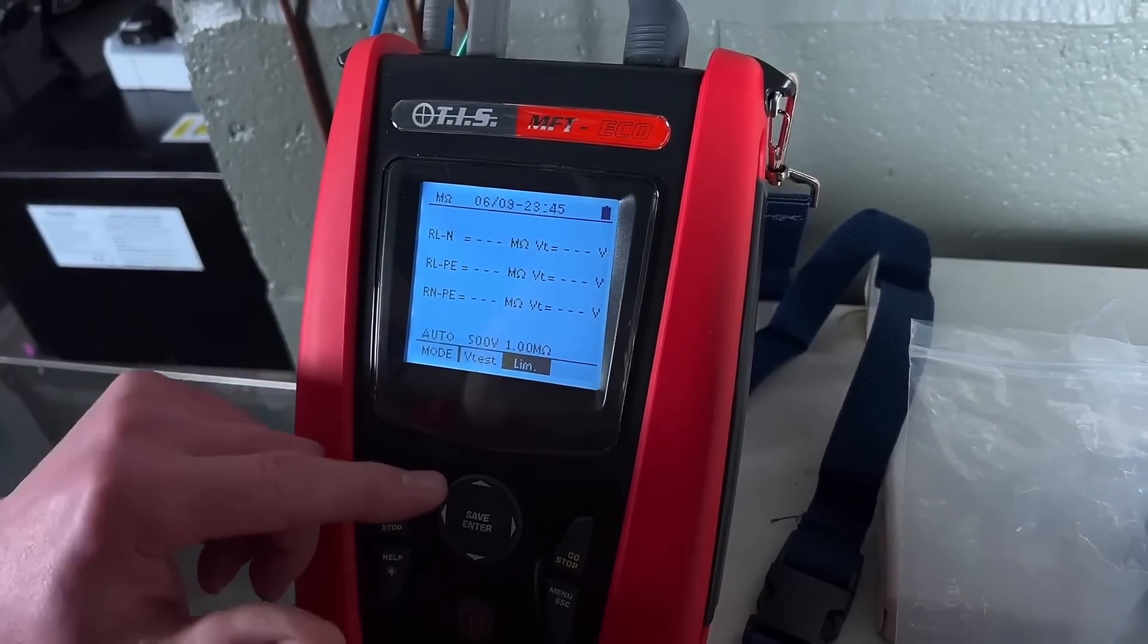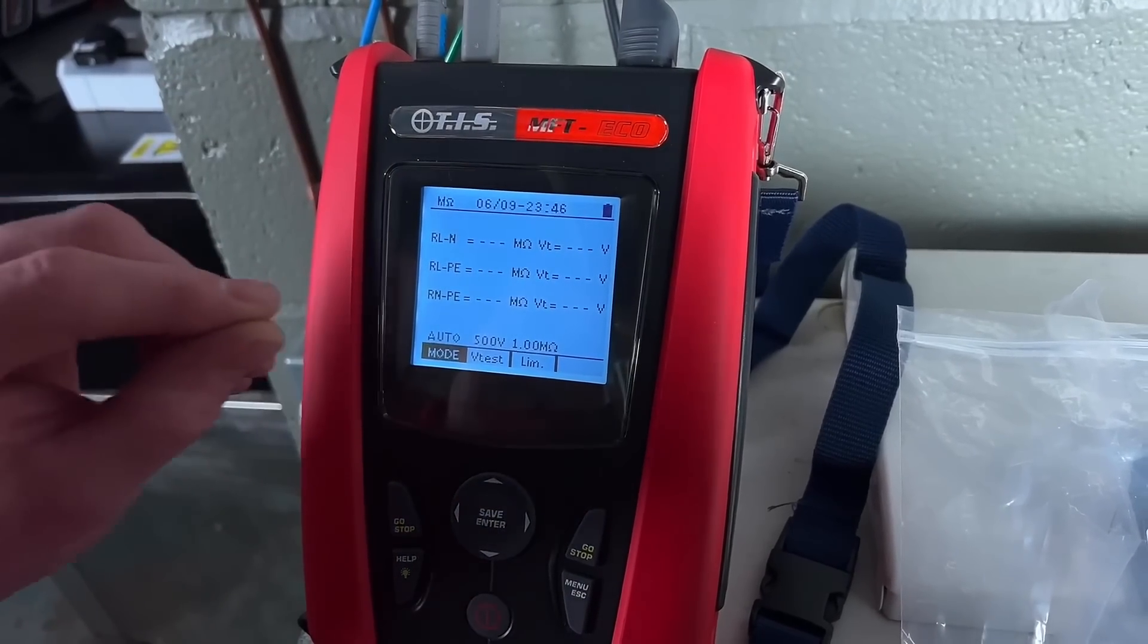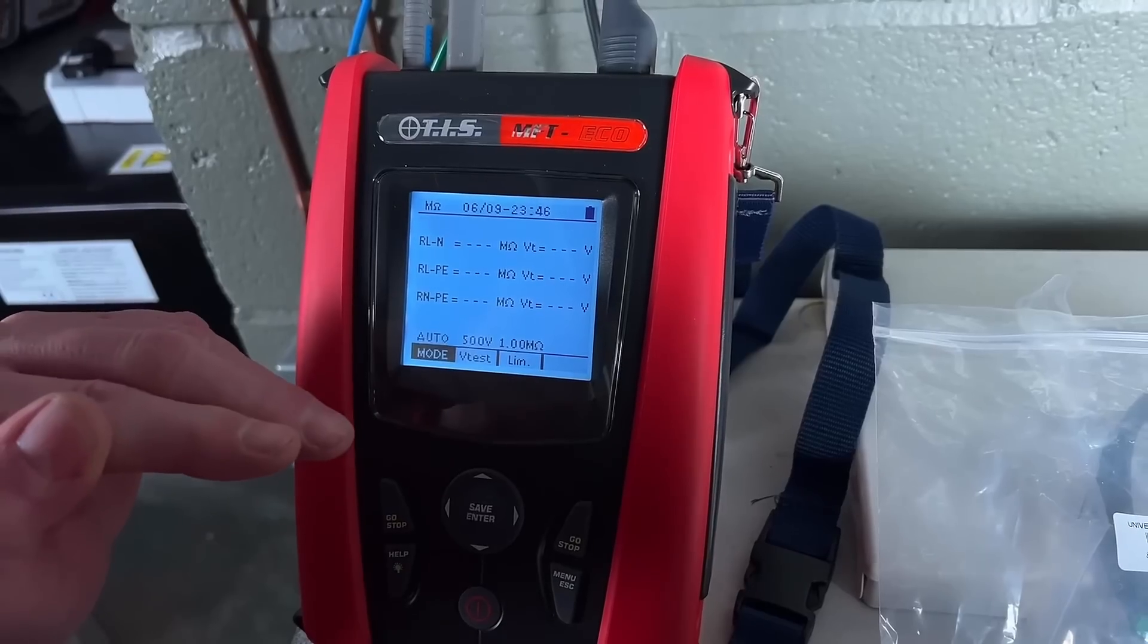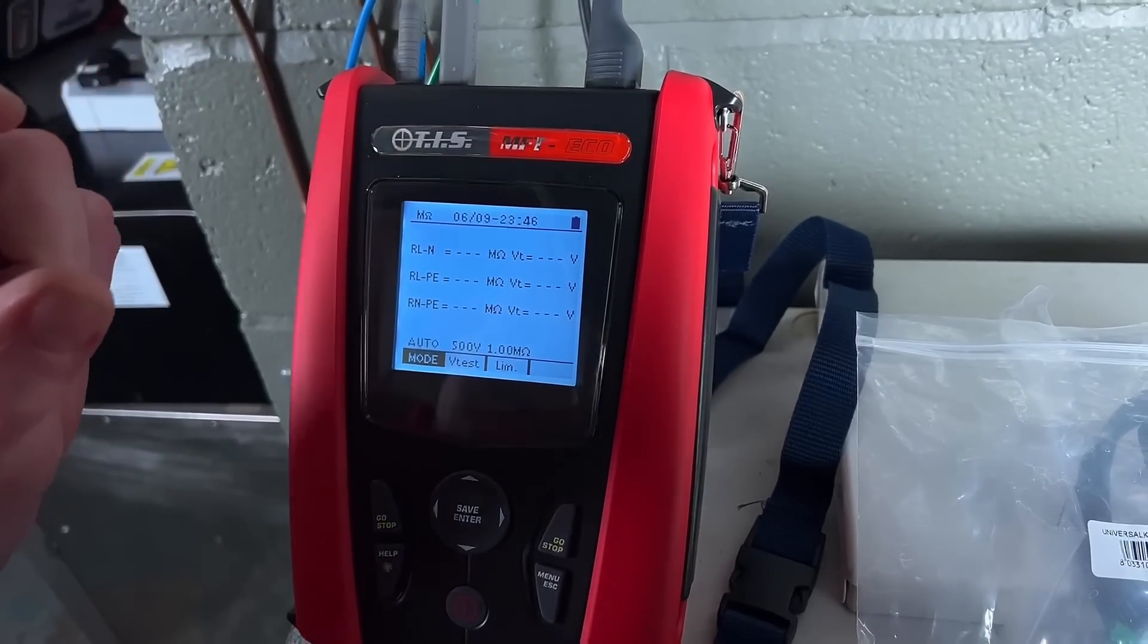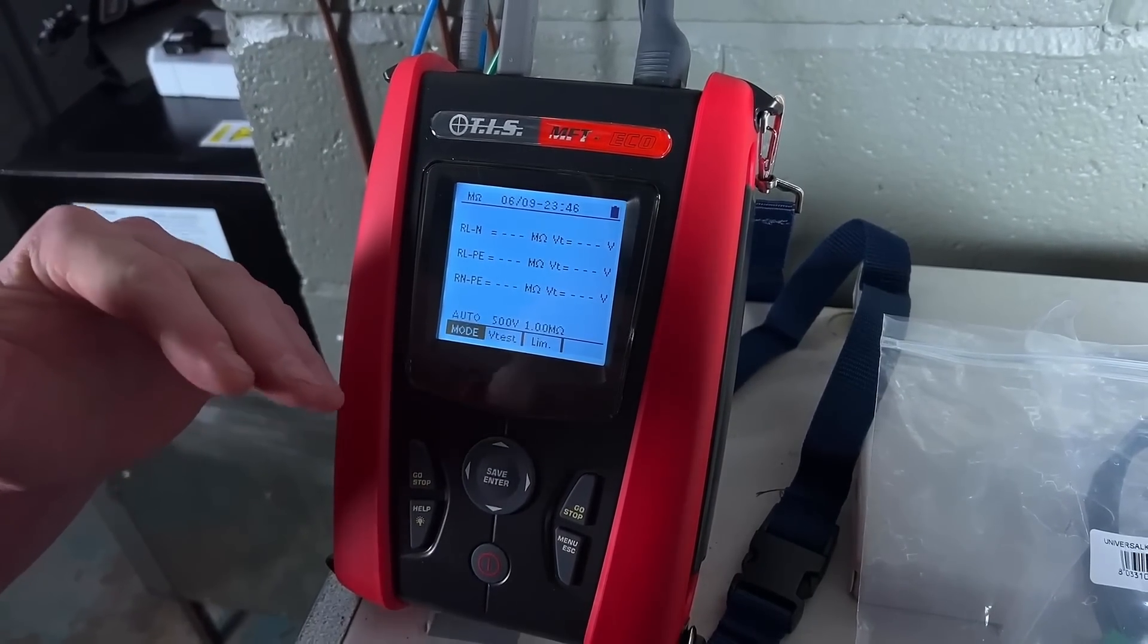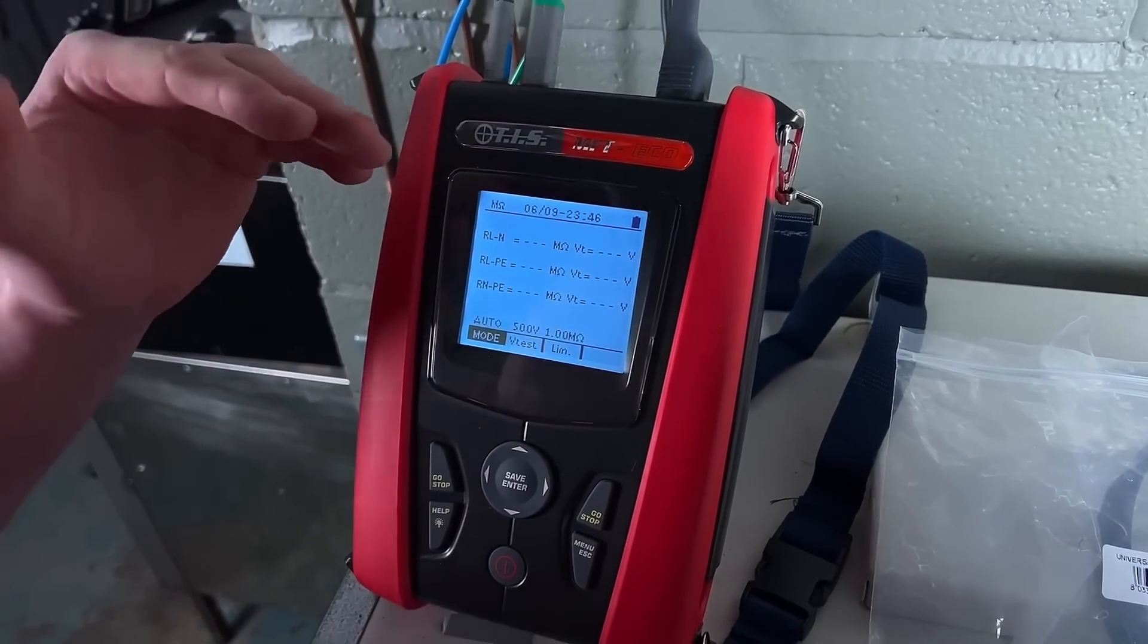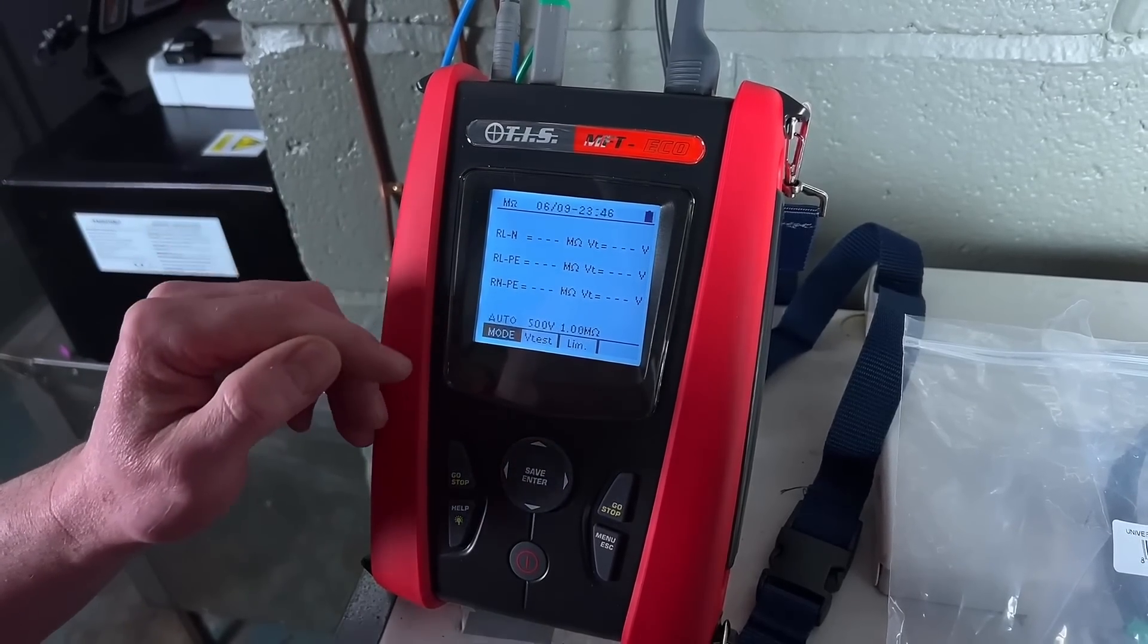But what's really good on this auto test: when I've connected all three leads, it will actually first of all apply a voltage that starts to climb between my line and neutral conductors. If it detects something's there, it will throttle back that voltage so it doesn't pass too high a voltage and damage it. In other words, it's a little Rick check. So if Rick hasn't removed all the loads, it will spot that for me before carrying out the test between our line and protective earth and neutral and protective earth.